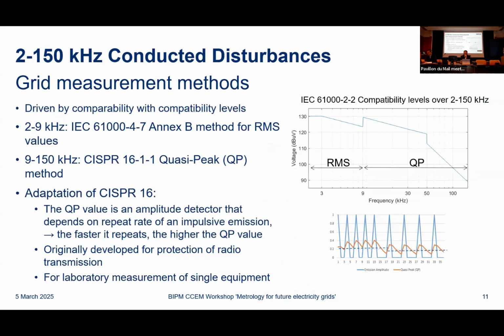For the grid measurement method, there were different candidate methods under discussion, but the key driver for what the method should look like comes from the compatibility levels, because you want to be able to compare the result of your measurement method with the compatibility level to check whether the disturbance levels in the grid are compliant. The way the framework looks at the moment, from 2 kilohertz to 9 kilohertz the compatibility level is defined as an RMS value. The computation of that RMS value is defined in the 61000-4-7 Annex B standard, the standard for harmonics measurement methods. It's quite similar to the measurement methods for harmonics, so it's relatively familiar for the power quality community.